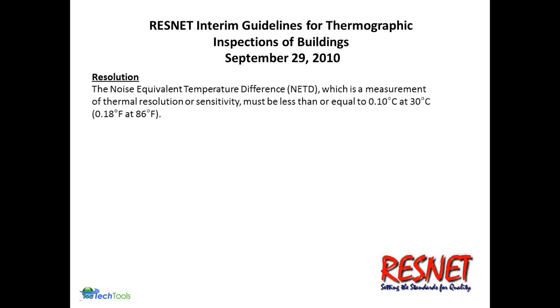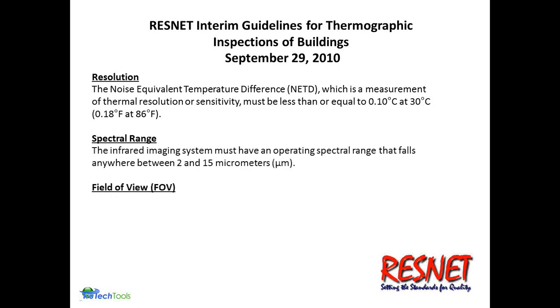So some guidelines from RESNET, which I've mentioned a couple times here. Resolution is just the noise equivalent temperature difference. You'll see that in the spec listed as the NETD. It's an important spec to consider when doing a building envelope scan, though not as important for electrical and mechanical scans in the industrial marketplace. The spectral range generally falls between 2 and 15 microns. For building envelope work, the key range is generally listed as 8 to 12 or 8 to 14 microns.